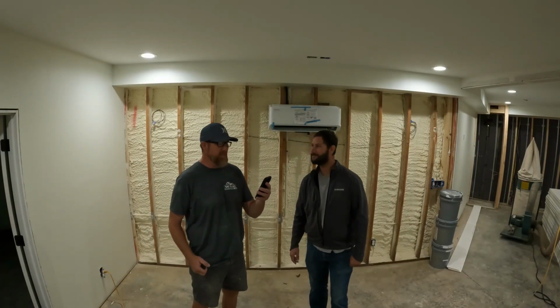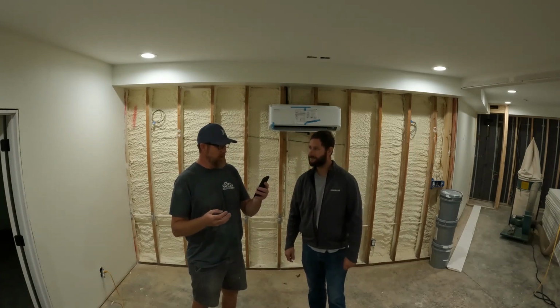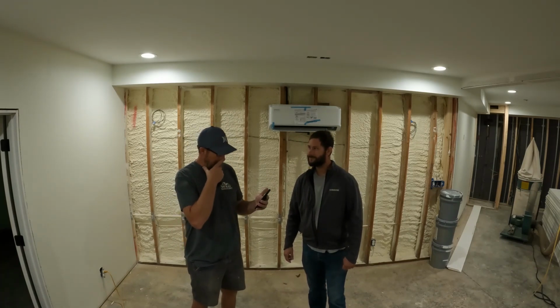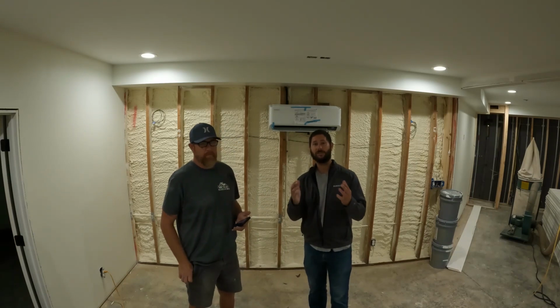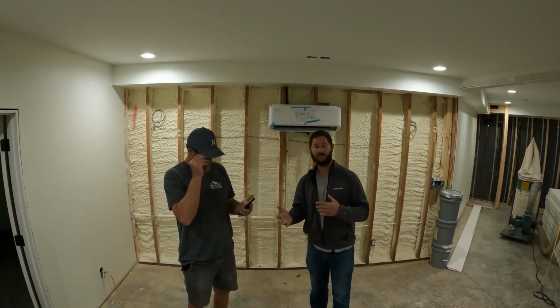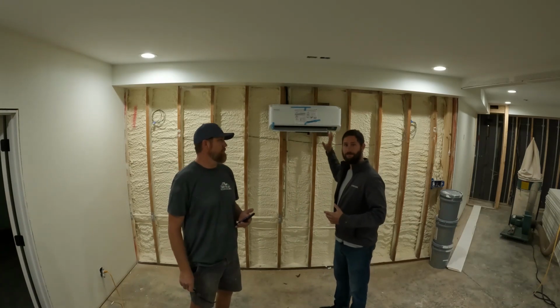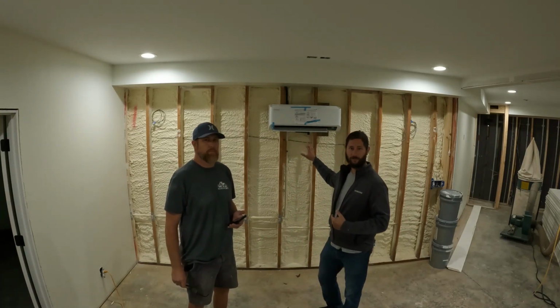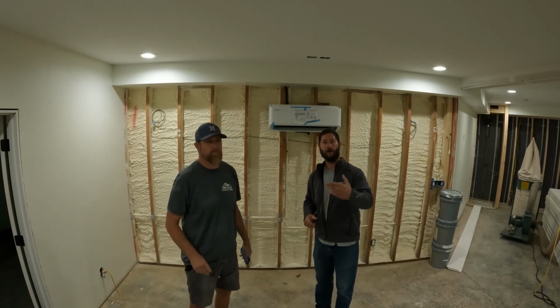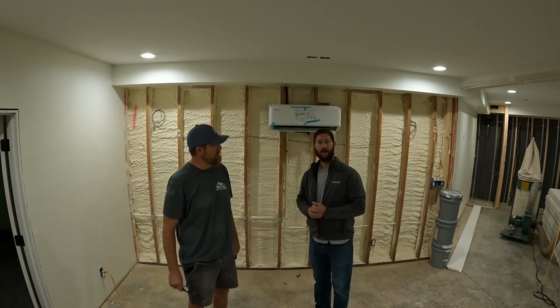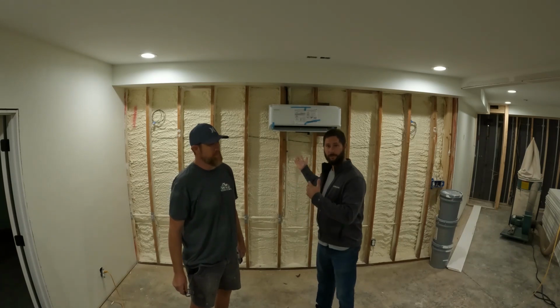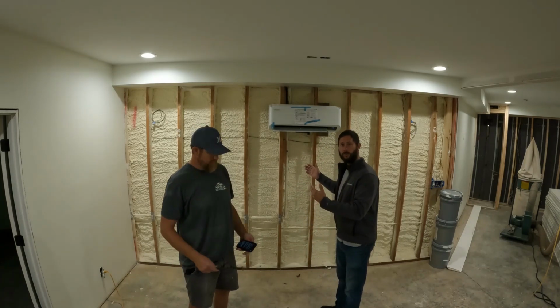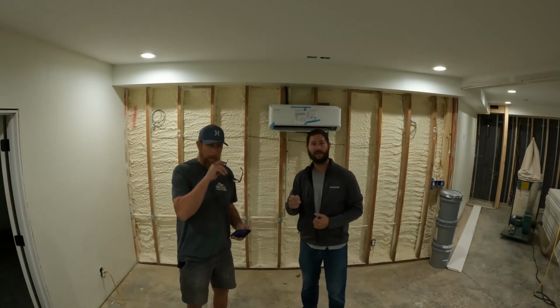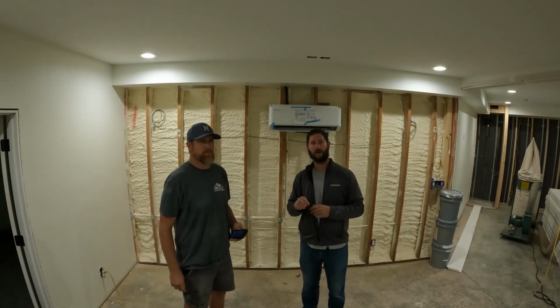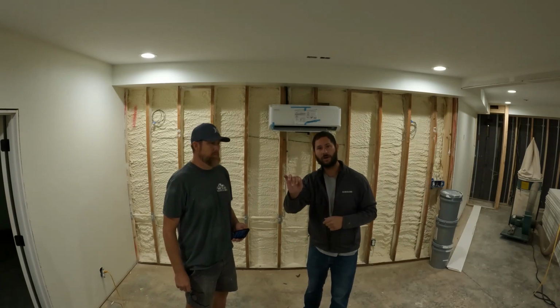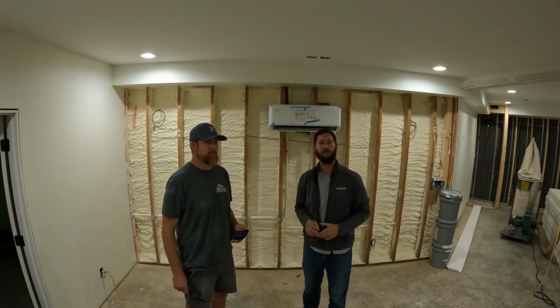All right, so what are some of the benefits to using a mini split system versus a standard duct system? All right, so the standard duct system is usually a single stage unit. You can get two stage, you can get variable speed, but what's great about mini splits is they are variable speed. They're not single stage, so they don't just come on and pull 100% of whatever the rated breaker is for that equipment. They have an ability to vary the capacity. It's like having a VFD on a motor, a variable frequency drive, or a knob where you can just turn the capacity up whenever you need it.